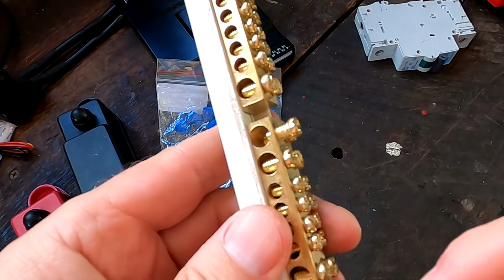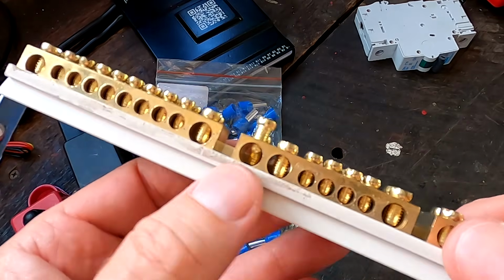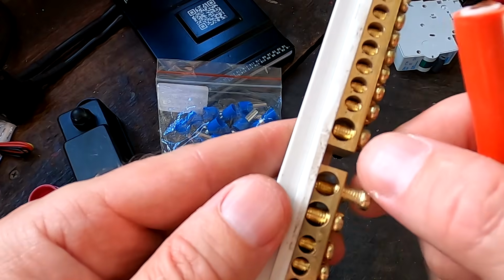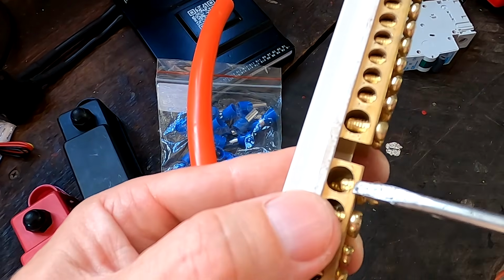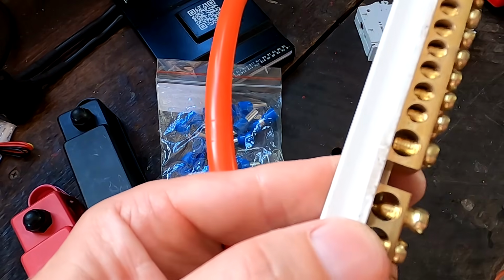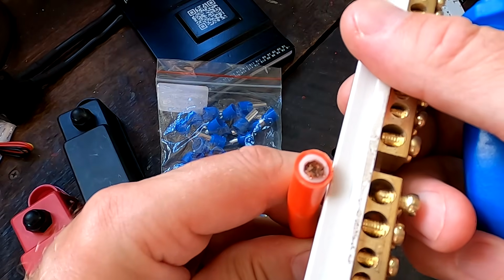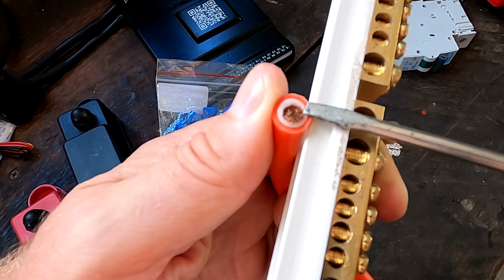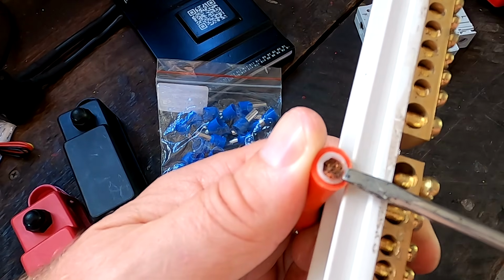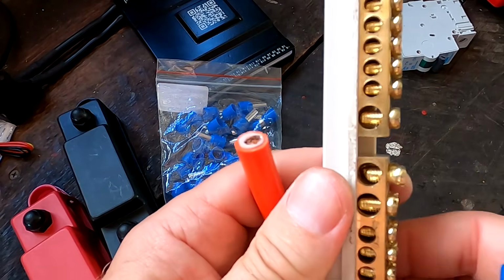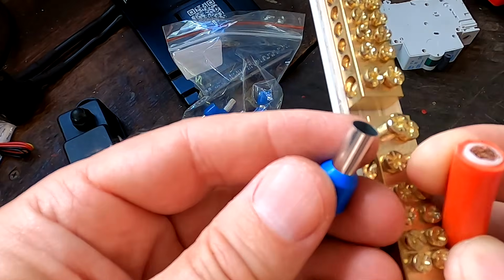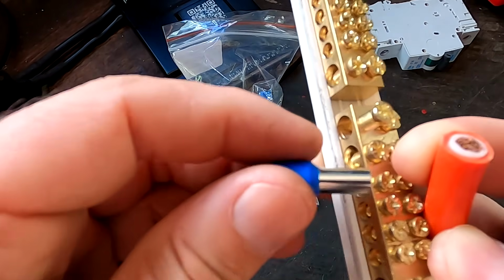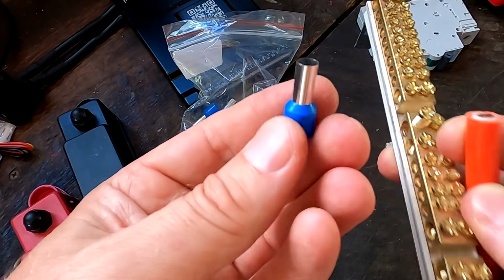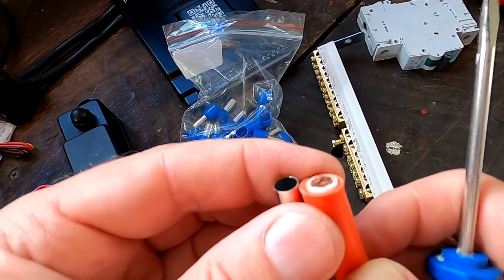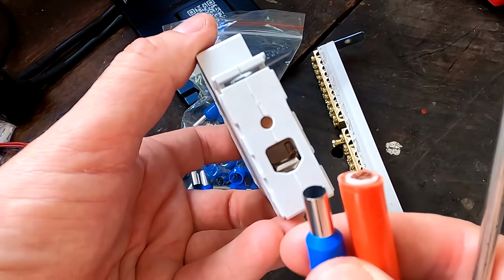But here on the other side, if you want to put one of these cables into a screw terminal, like these ones here, for example, they don't have any mechanics. See, there's the bare screw coming down, and the screw actually is pushing into your cable. If you have these fine stranded cables, this will kill it. The force of the screw coming down here will potentially cut off some of your strands, and therefore you have a smaller diameter of cable. In cases of using these screw terminals, you always have to ferrule these cables. The ferrule in this case will protect the fine strands inside your cable from the damage of the screw. And I'm a big fan of ferrules, so I always ferrule these cables. They're always getting a proper termination. Even if I use these normal circuit breakers, I always use a ferrule. Always. Fine stranded cables, I always ferrule.